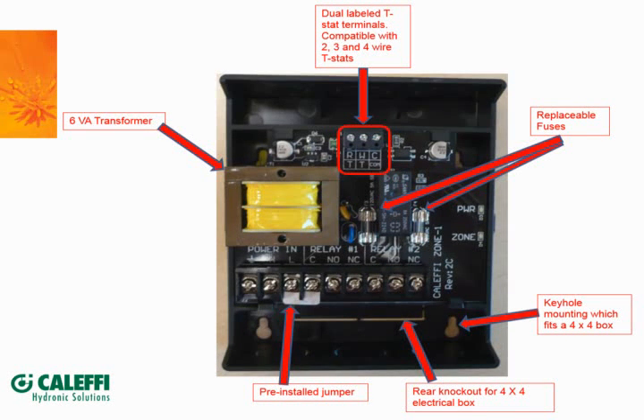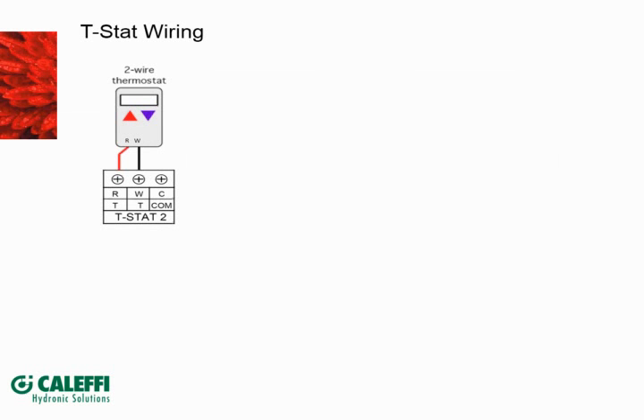Okay. So getting into the stat wiring, the 2-wire stats, it doesn't matter if it's battery operated, a mercury bulb, a bimetallic, or a power stealing stat. They're all going to connect up to the R and the W contacts. The R is really your 24-volt supply. C is common, so if you put a voltmeter between R and C, you're going to see 24 volts AC all the time. What fires the unit is when R gets connected to W. So your 2-wire stat, if it's just basically like a dry contact, it's going to bring R and pull it back to W, and that's what initiates the heat demand.